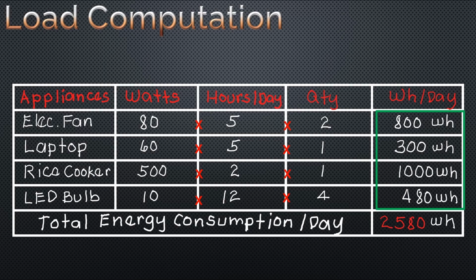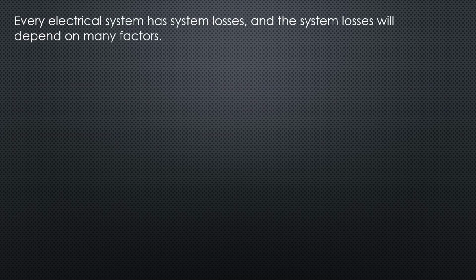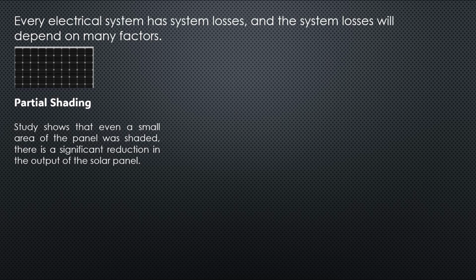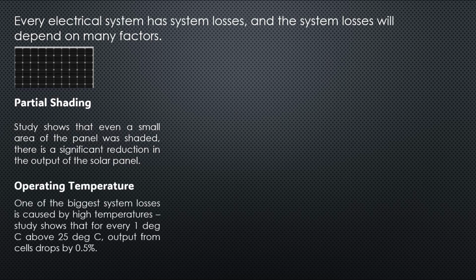But supplying this total energy from the source, which is from solar panel, kailangan din natin i-consider ang power loss sa bawat equipment, katulad ng solar panels, inverter, at mga wires, bago ito makarating sa mga loads. Dapat ninyong tandaan na every electrical system has system losses. And the system losses will depend on many factors. For example, in the solar panels, maraming factors ang pwedeng makaapekto sa performance nito. Una diyan na may malaking reduction sa output ng solar panels ay tinatawag na partial shading. Like for example, the shading coming from nearby trees or any structures. Another factors that significantly affect the output of the panel is the operating temperature.